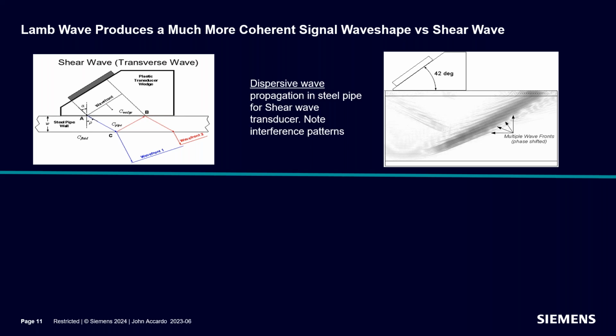And the issue with that is that when that wave reflects off the inner wall and comes back up, it's not necessarily in sync with the wave that's arriving at that point from the transducer. So if you think of a transducer wave as coming in, when that wave arrives at the pipe wall, that reflected wave inside the pipe wall isn't necessarily combining with it. It may be clashing with it, as a matter of fact. And so you get a dispersive wave. So the propagation down the pipe wall is a very noisy one. And you could see multiple wave fronts on the right side, and you see this cross-hatching pattern in the pipe wall. And so it disperses as it travels down the pipe wall. And the shape of it varies depending upon where you pick it up.